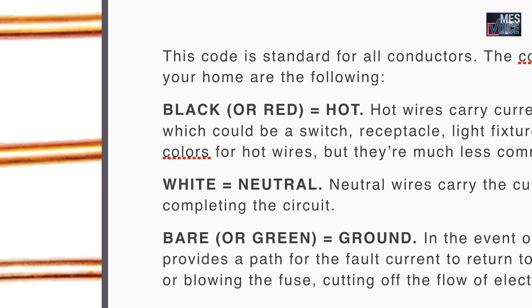This slide explains the color coding standard for all conductors. Black or red wires are always used as live or hot wires for carrying current from source to device. White wires are used as neutral wires for carrying current back from devices to the sources, completing the current loop. Bare or green wires are generally used as ground wires, providing a path for fault or excess current back to ground, fuse or breaker from the affected devices.